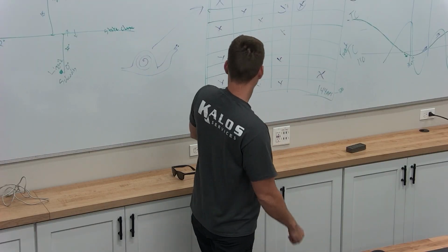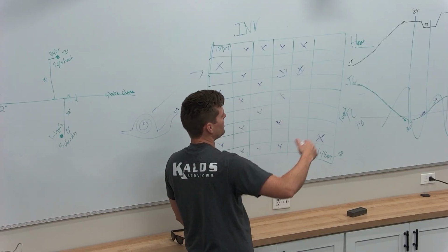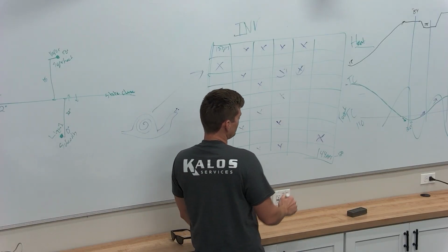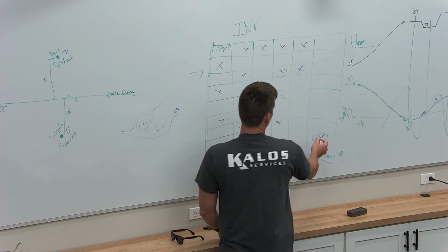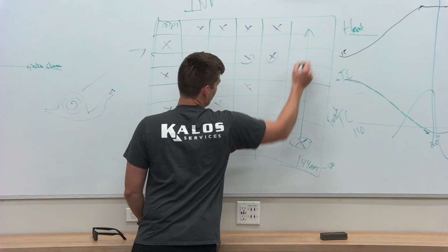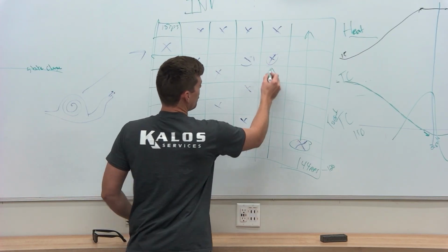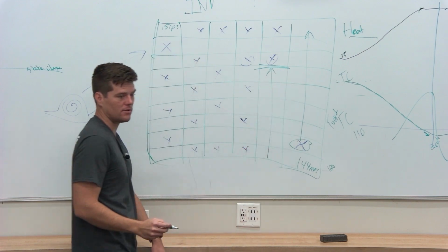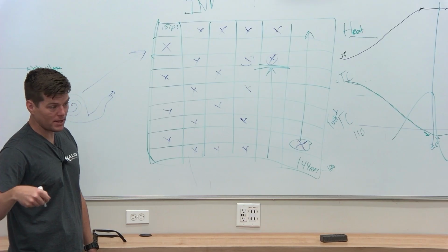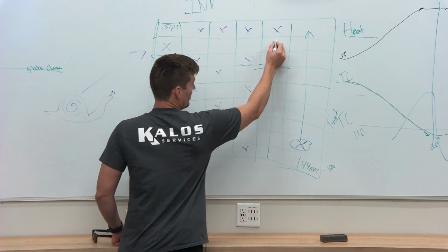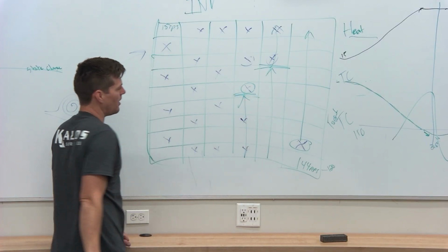Here's how it works. Discharge temperature on the compressor gets really high, 227 degrees. And let's say it's down here at this compressor speed. The unit goes, whoa, whoa, whoa. Go back all the way to here and stay here. You can't go above this line, right? Stop. And if the discharge temperature doesn't come down after a minute, 2 minutes, then it says, okay, go back some more. Come back here to this line. Don't go above that line.